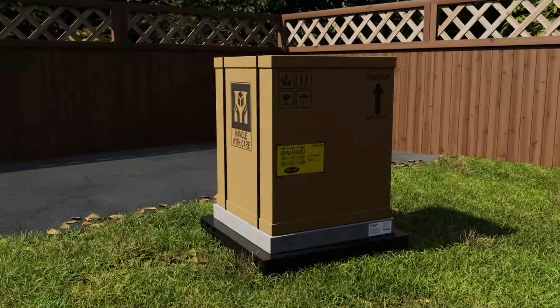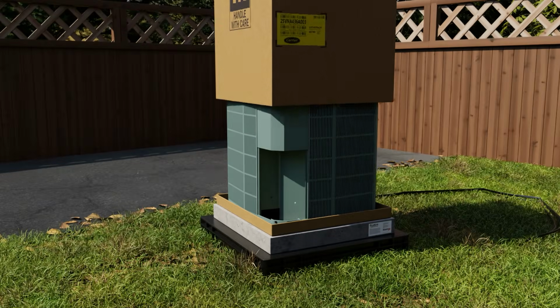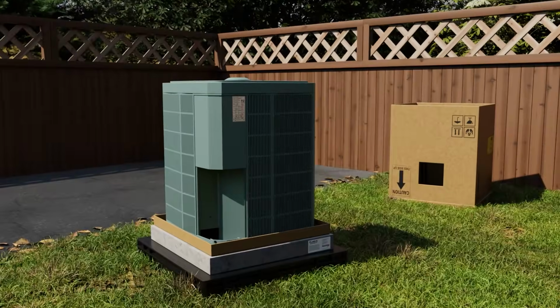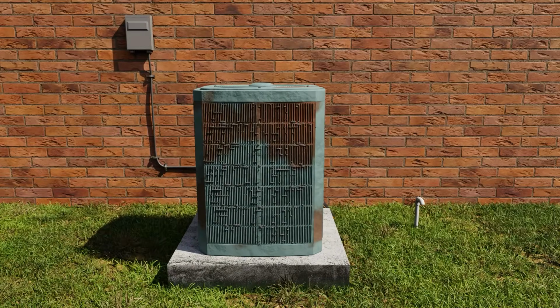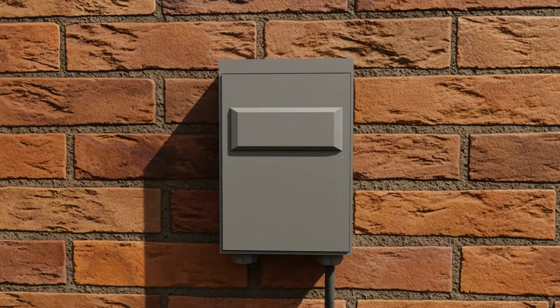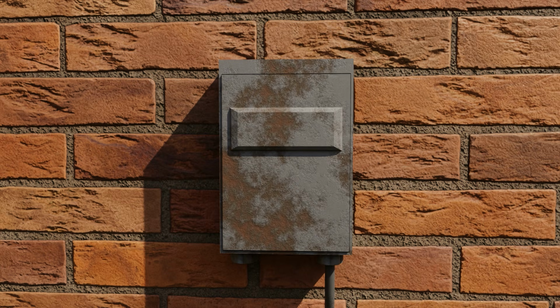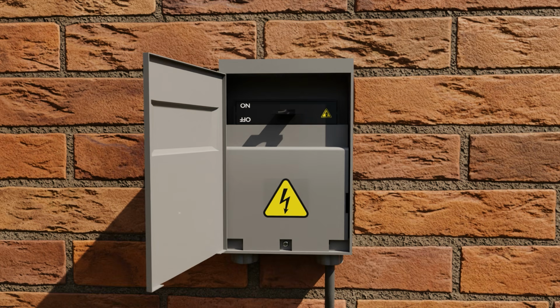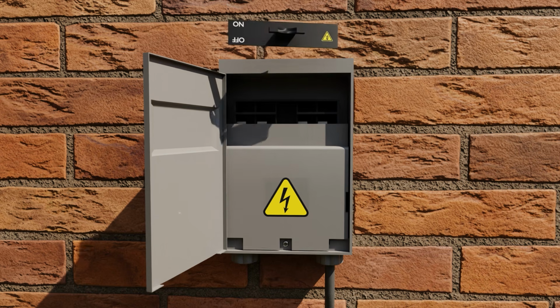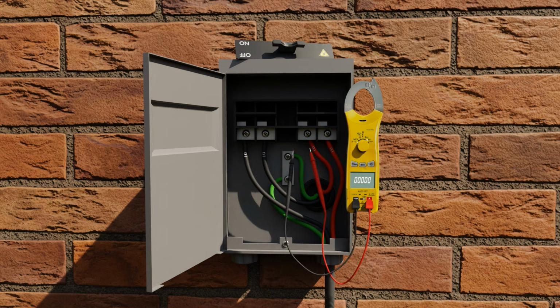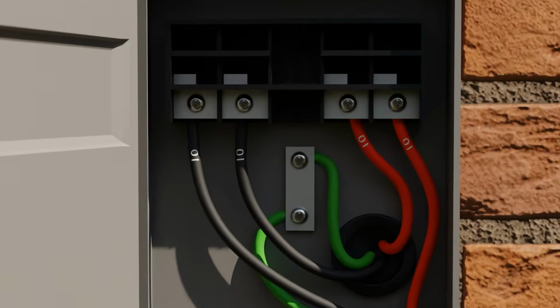Next, unbox the unit. Where possible, use the box as your garbage bin to keep your workspace neat. Check your disconnect. The proposal will dictate whether or not it's to be replaced, but inspect it to make sure that it is in good and serviceable condition. In our market, we're licensed electricians, so we can replace those if they need to be replaced. Other markets may be different. Always safely remove the disconnect and test to make sure you do not have 240 volts from leg to leg, and then also check for 120 volts from leg to ground as shown.